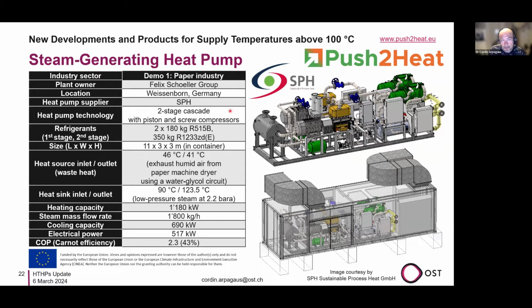So it's a 2-cascade system with piston and screw compressors. Here you can see the piston compressor, the motors, 2 compressors here, and here the screw compressors, the heat exchangers, and again here the steam generating heat exchanger. The refrigerant used is R515B in the first stage, and then R1233zd in the second stage. This is all on a rig, and then finally placed in a container solution, which you can see here on the bottom.